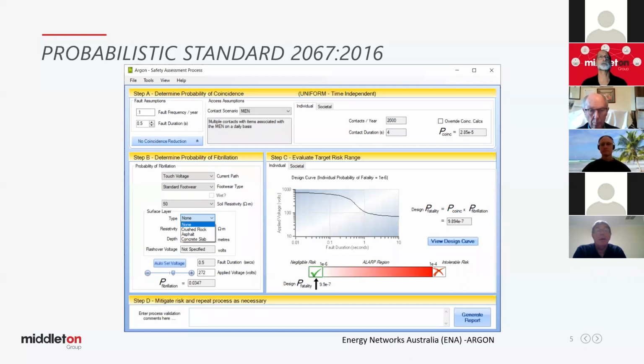There's other inputs to the left. If you look down, we can use this software to have a look at what touch voltage is allowable. We can also select step or hand-to-hand for the current path there. We can select different footwears, make it wet. We can change the soil resistivity of the surface, which will have a bearing on the amount of current that's going to flow through you. There's also surface layers there. You can see I've managed to highlight them, whether we've got crushed rock, asphalt or a concrete slab. This will change the resistance to the voltage, obviously, and have an effect on the amount of current that will flow through your body and the risks involved with causing ventricular fibrillation.